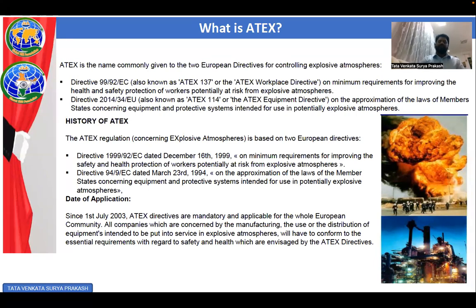We will go through the history of ATEX. The ATEX regulation is based on European directives, starting back around 1999 on minimum requirements for improving the safety and health protection of workers potentially at risk from explosive atmospheres. The directive first came into implementation with the purpose of protecting workers in explosive environments. Then it was extended to cover equipment and protective systems, specifying how they have to be designed, since workers are prone to exposure in such environments. So equipment also has to meet certain criteria when placed in an atmosphere where explosion can happen.